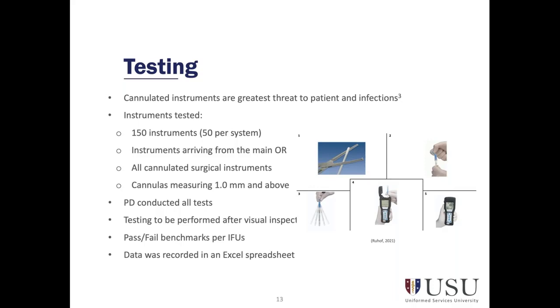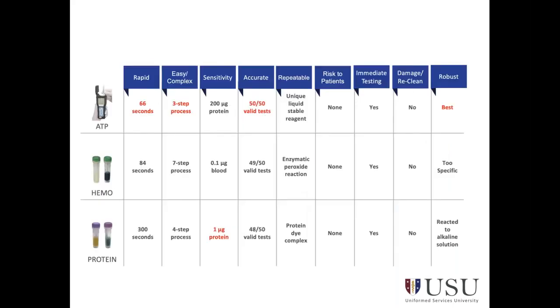The author used a nut and bolt gauge to measure the diameter of each cannulated instrument to verify that the instrument met the inclusion criteria and to select the corresponding testing swab before testing. In addition to test scores, data gathered included test results, whether it was pass or fail. If it was an RLU, then I would annotate the number reflected on the screen of the handheld device, nomenclature, surgical specialty, the diameter of each instrument, and the time required to conduct each test. I'll talk more about that timing later in the next slide.